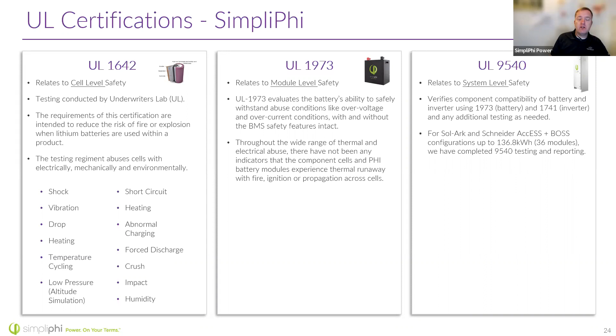So again, the 9540A is a test protocol that informs the parameters of battery safety and the installation conditions. That's what allows us in our installation manual, for example, to call out closer clearances between equipment than might otherwise be needed if we were looking at, say, the NFPA reports.